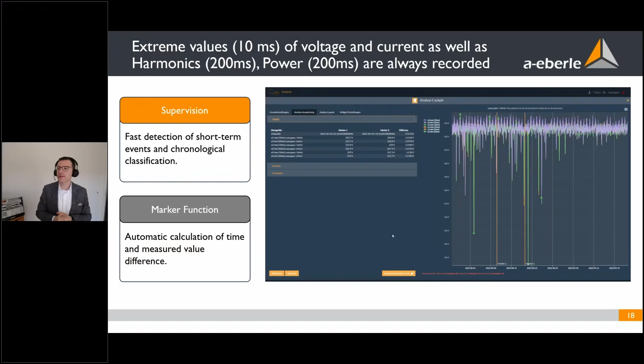And harmonics is really interesting, because the evaluation of harmonics is based on 10-minute average interval mainly, in the worldwide standardization. But I know there is an ongoing discussion, because if you switch on and switch off an inverter, like my PV power plant at home, for example, then especially in the first minutes, I have very much higher harmonics, and these are the extreme values. And you can see, for example, here an example of 3-month data approximately from the voltages, and the same you can see as well as for the harmonics in that way.